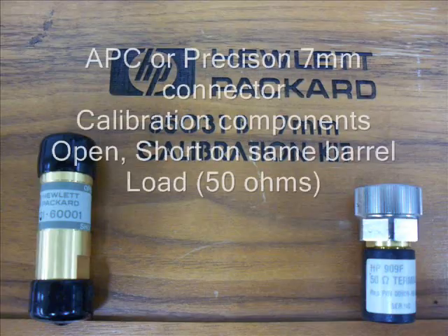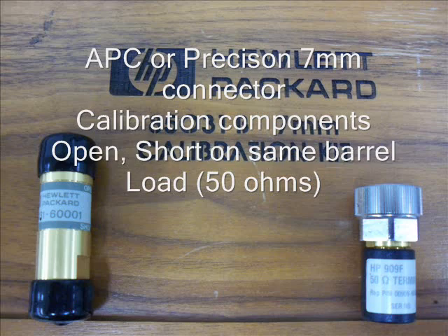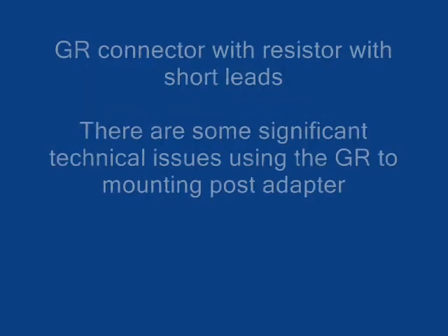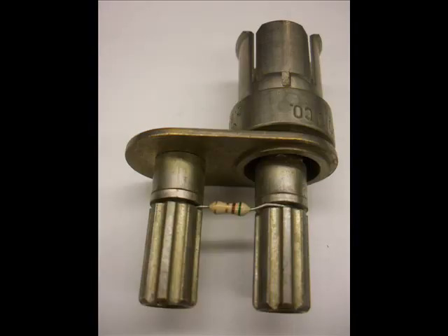So we need to add a similar connector to what we calibrated the connector with, so GR to GR, N to N, in order to maintain that phase reference.